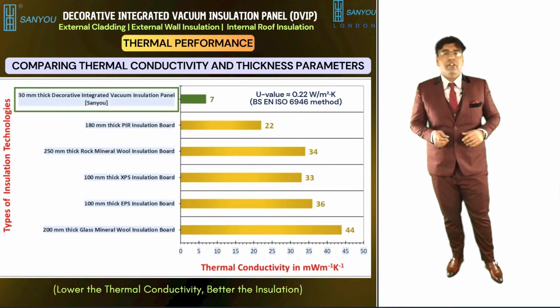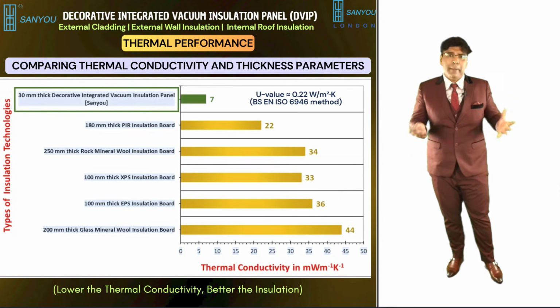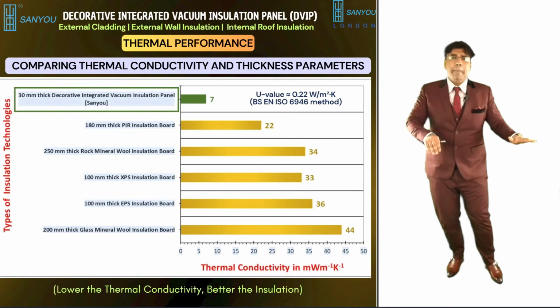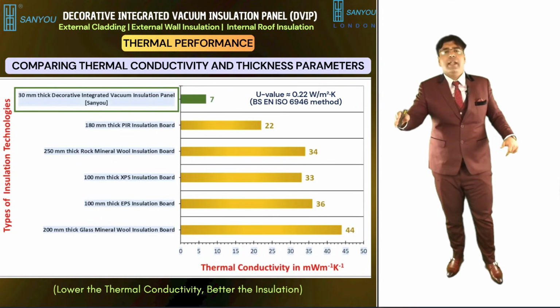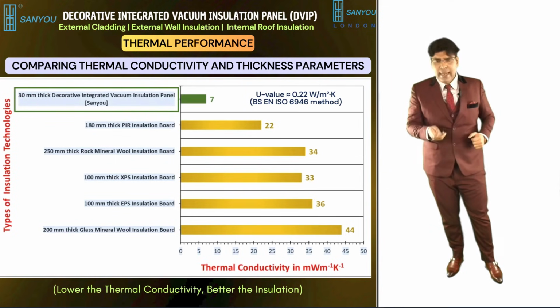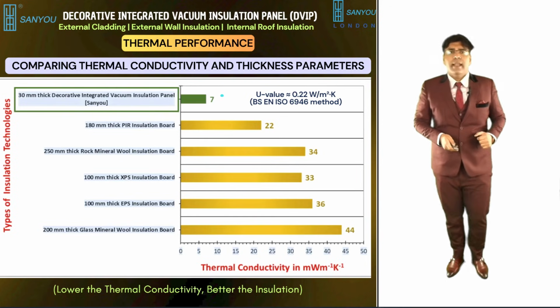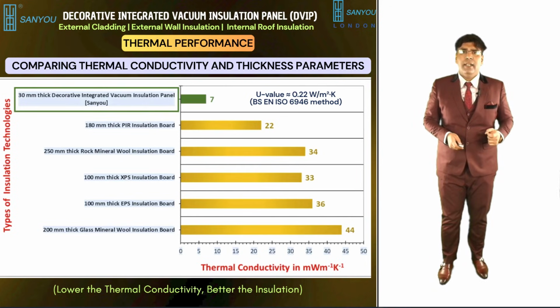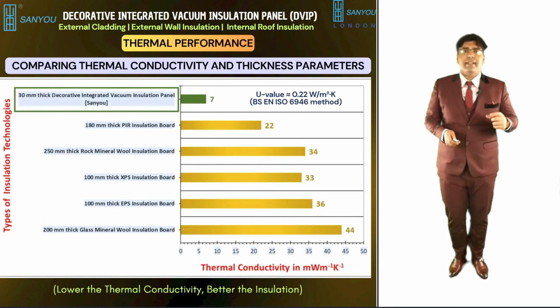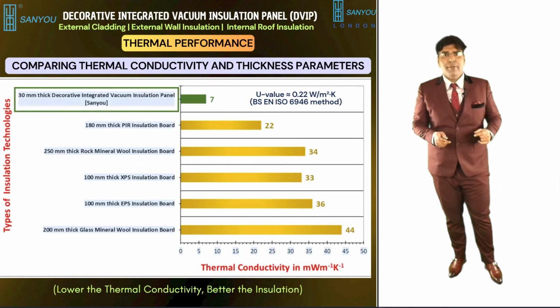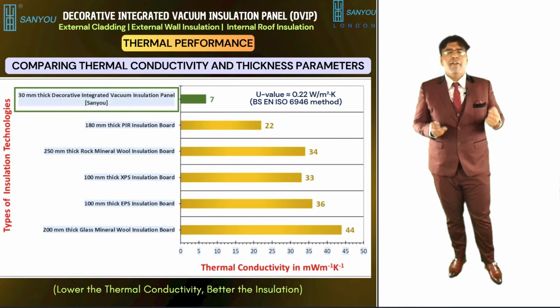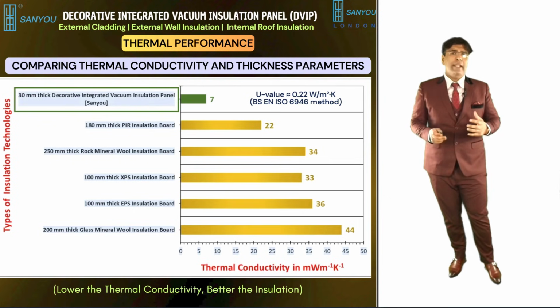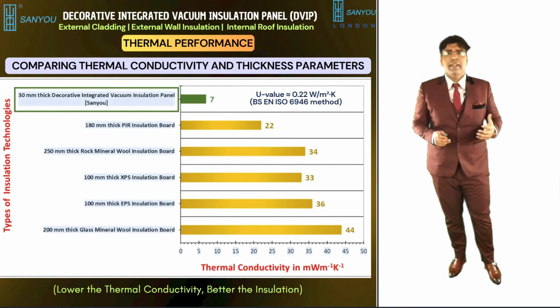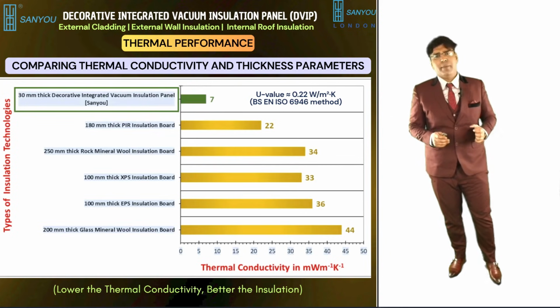To compare the thermal conductivity and thickness parameters: the lower the thermal conductivity, the better the insulation, and the lower the cooling or heating energy loss. What we see here is our 30 mm thick decorative integrated vacuum insulation panel that has a thermal conductivity of 7 mW per meter per Kelvin with a U value of 0.22, offering the best thermal performance, far better than any conventional insulation materials available today. For example, even at 250 mm thickness, rock mineral wool still has a thermal conductivity of 34 mW per meter per Kelvin.